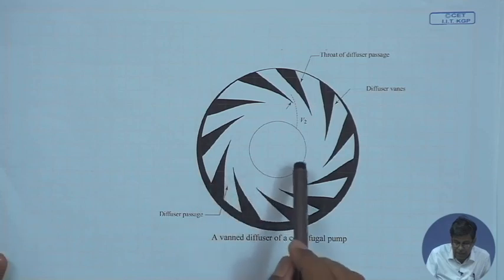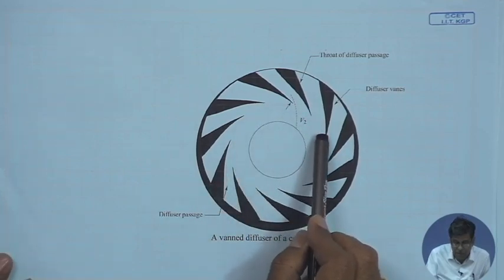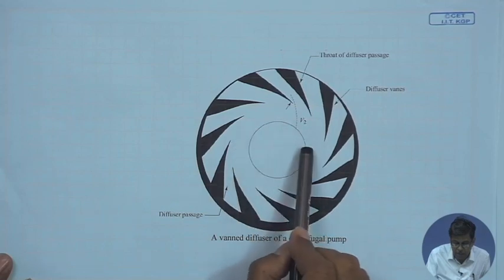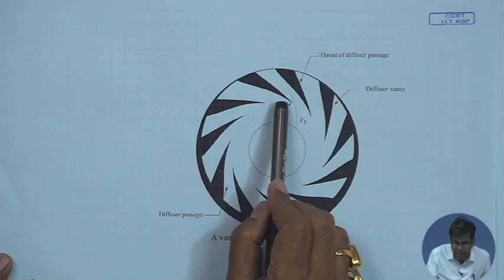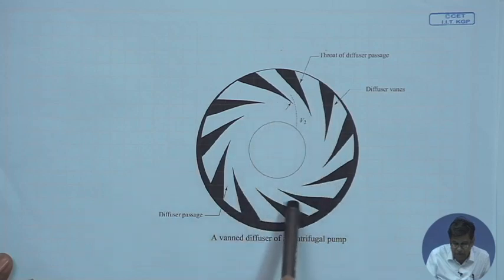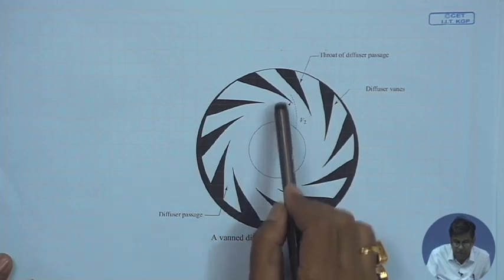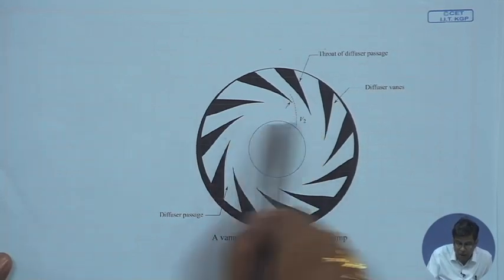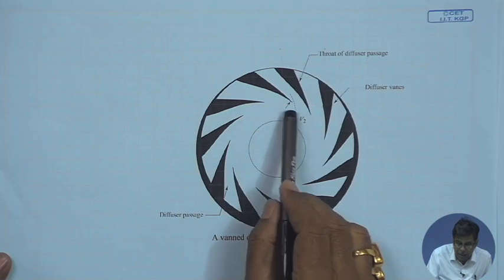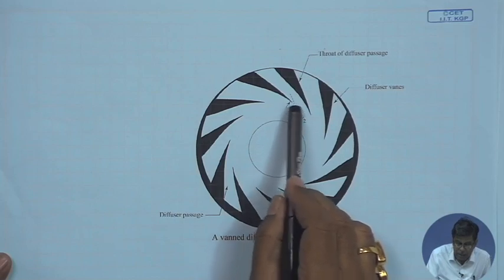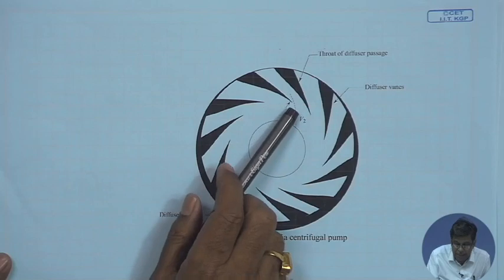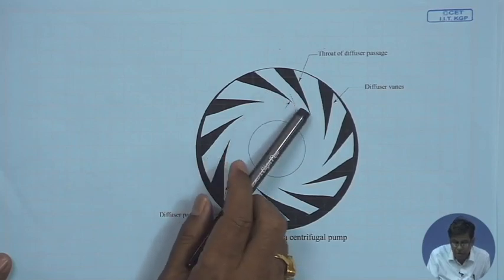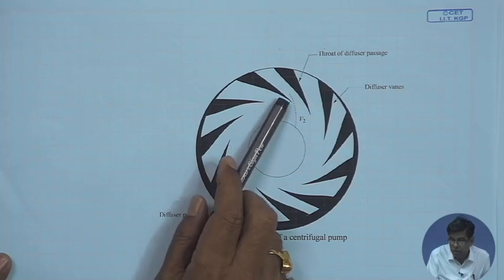One interesting point is that there is always a vaneless space between the impeller outer periphery and the entry to the ring of diffuser blades. This vaneless space is provided to accommodate the spiral vortex flow, directing the flow such that there is a shockless, proper entry to the diffuser vane without much loss. That is why a vaneless space is given.